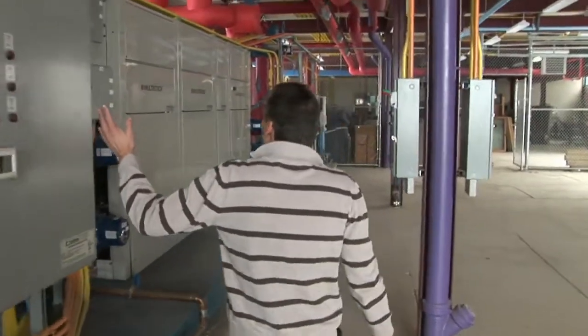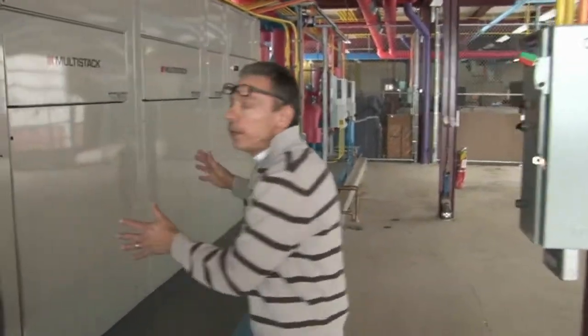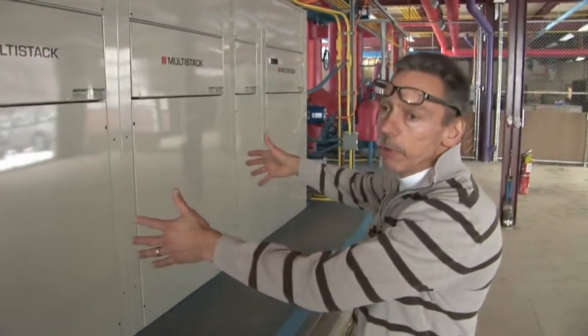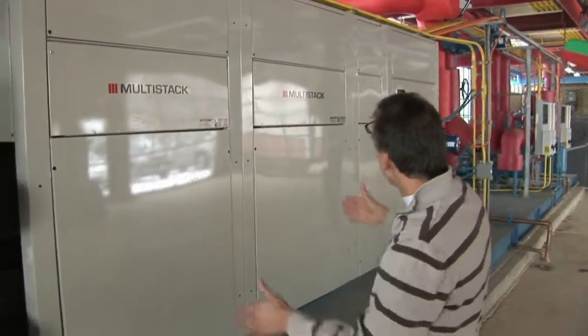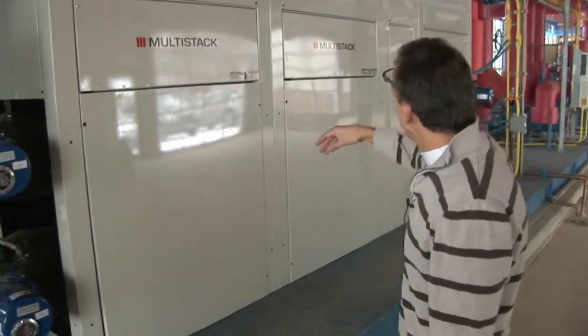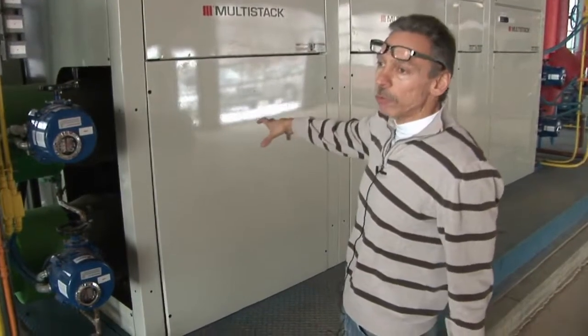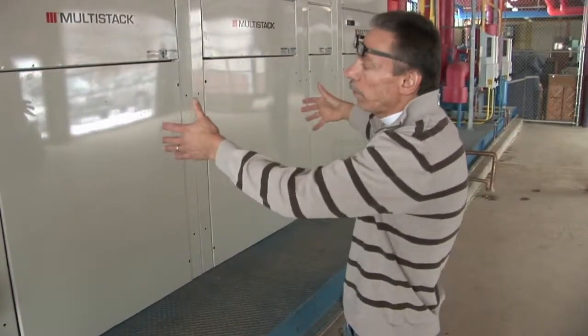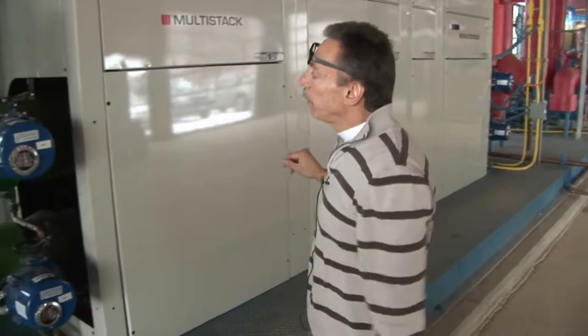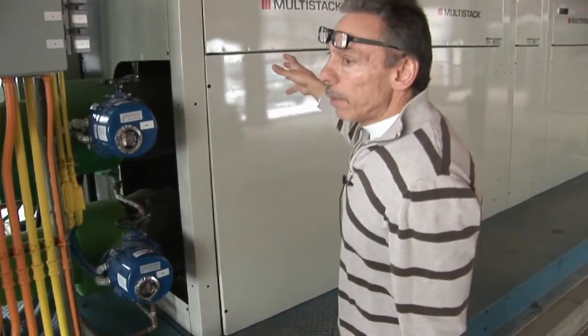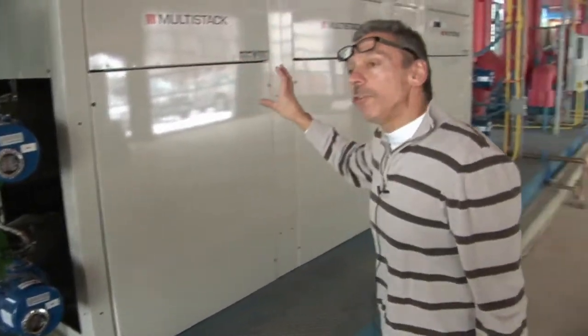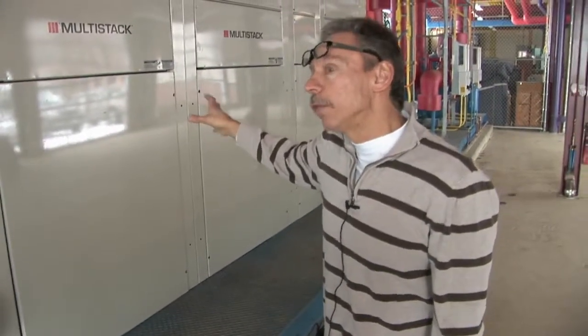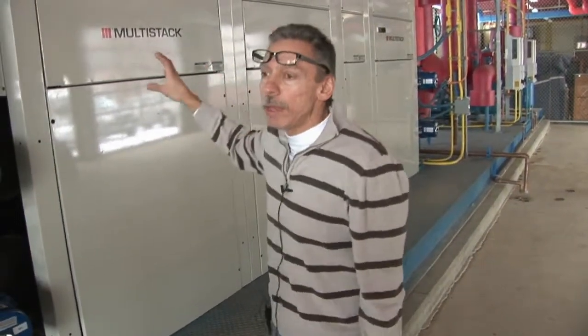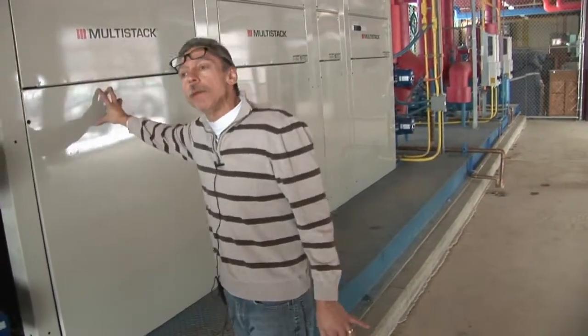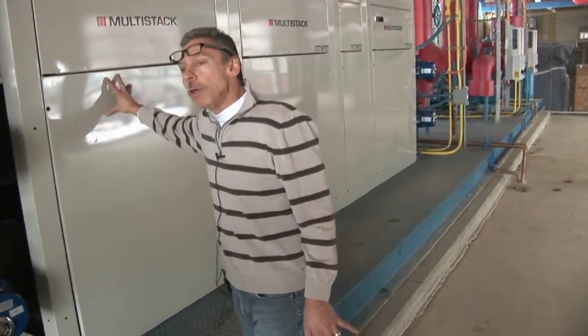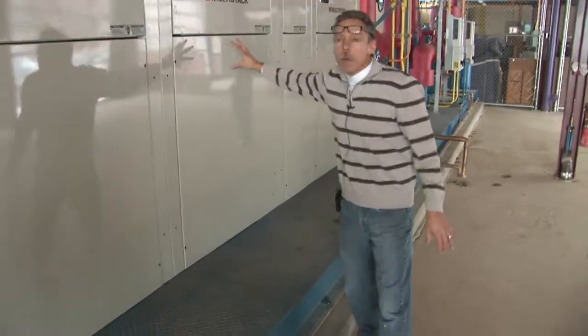So the water comes into the machine, feeds directly into these heater chillers, these multi-stack units. There's 3 modules. Each module has 4 compressors. These are heat pumps, so they're reversible. So they're heating now, and in the summer they chill? Well, they can also cool now if it's needed. So these 3 modules can be, one module can be in a heating dominant mode, providing heat to the buildings. This module could be cooling.